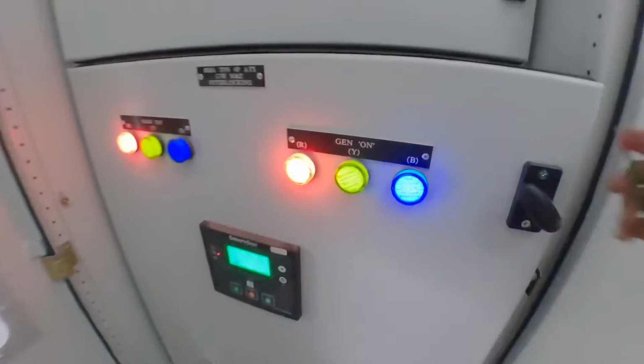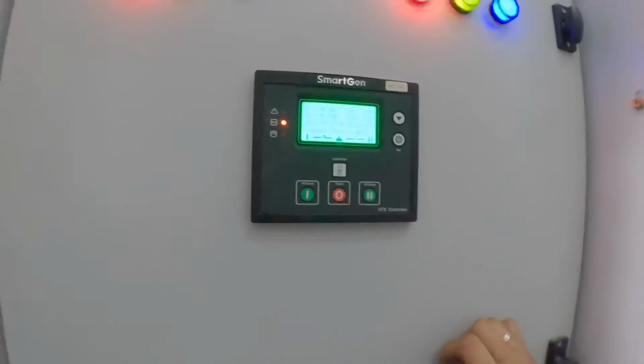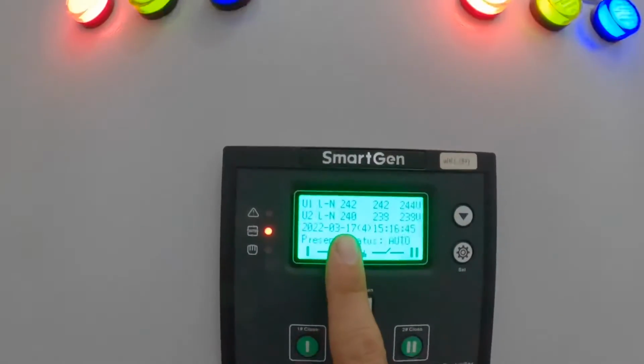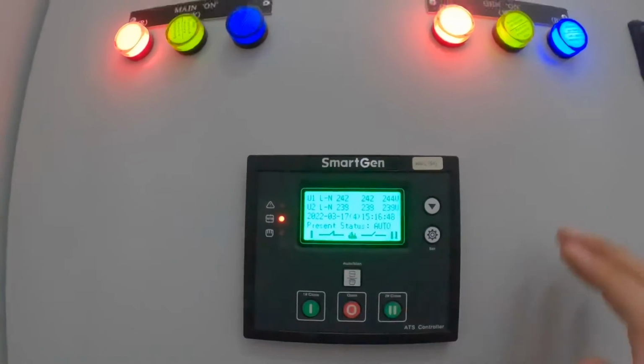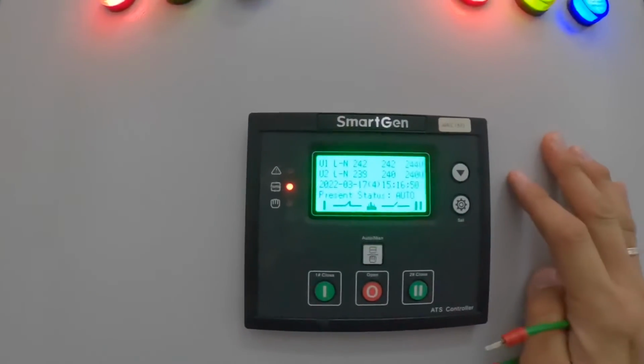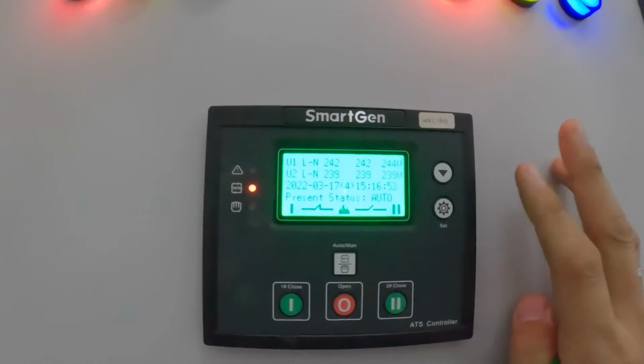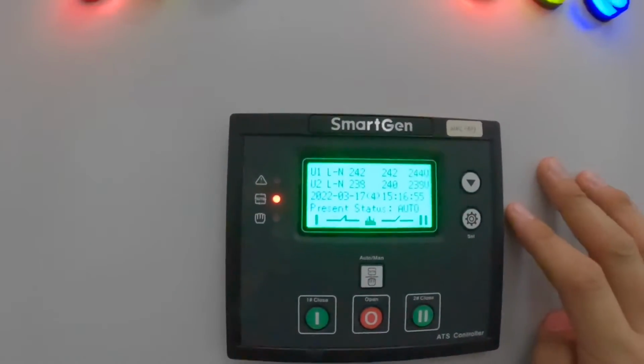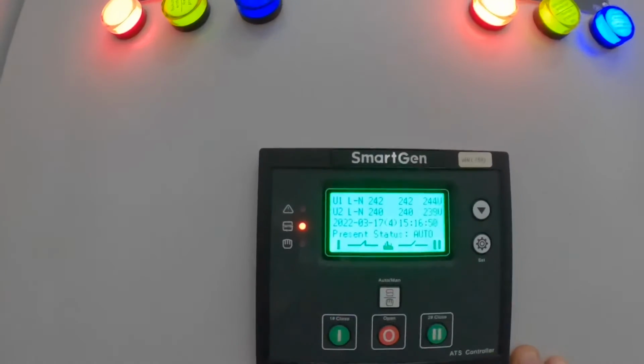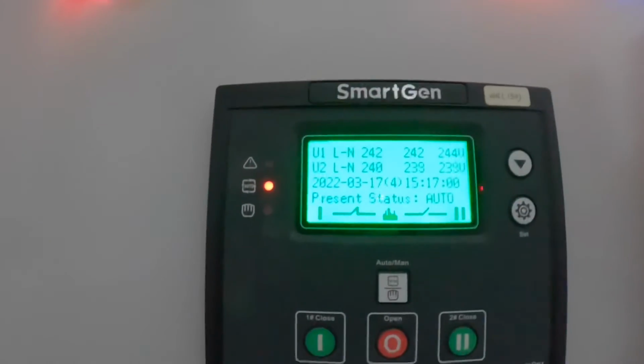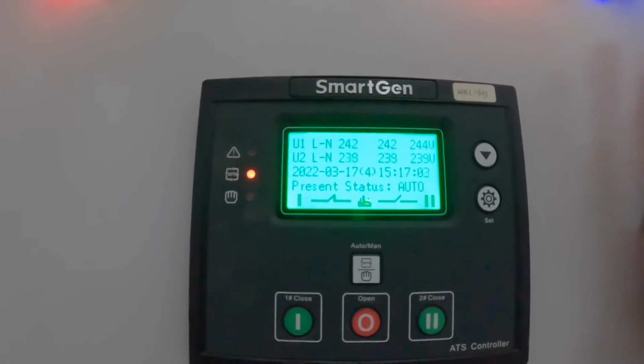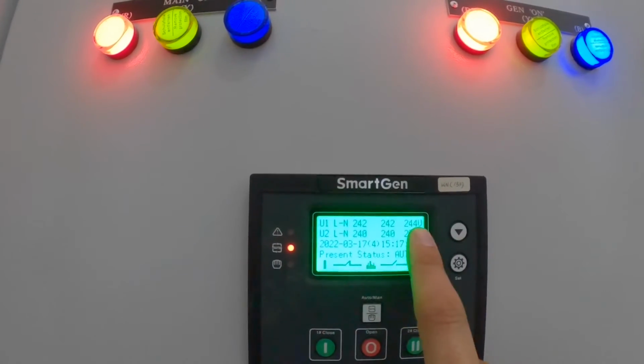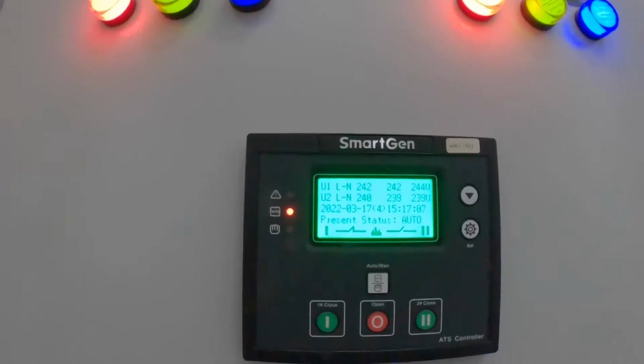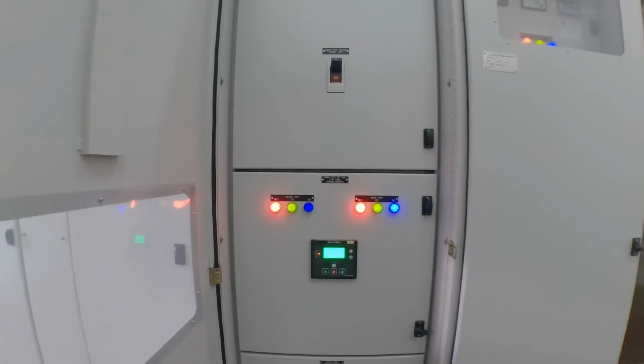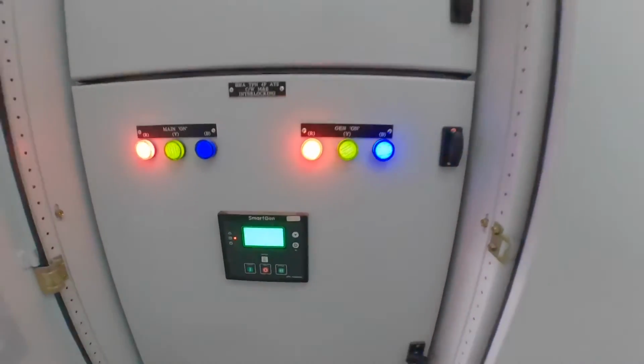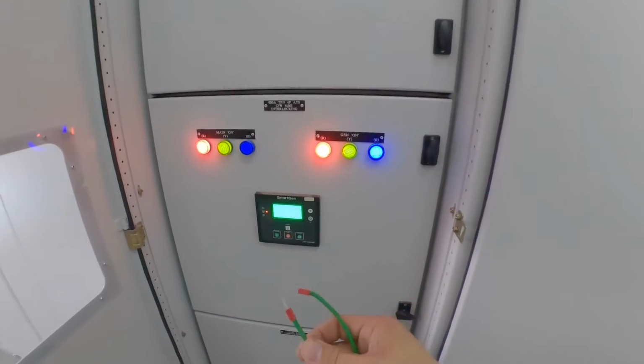Okay, the genset has run. Now from this ATS panel, we can witness that genset supply reaches here. The only difference is that the ATS doesn't change. It's still on the main supply contact. That means it doesn't operate because I just simulated a TNB power interruption signal. So this is the main supply. This is the genset supply. Later on, the genset will stop automatically because of the jumper wire I already removed.